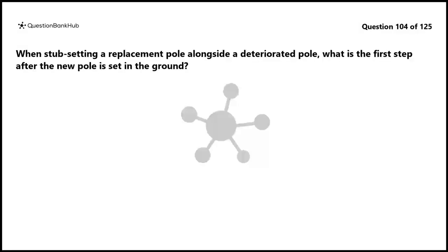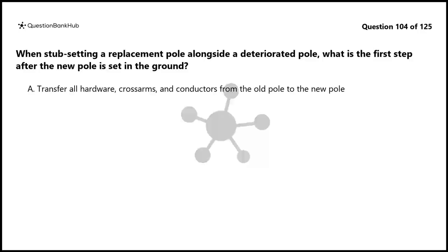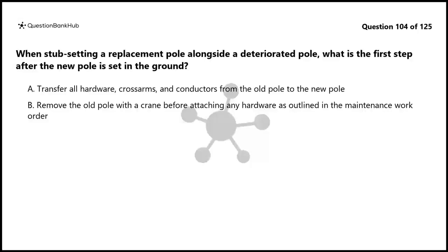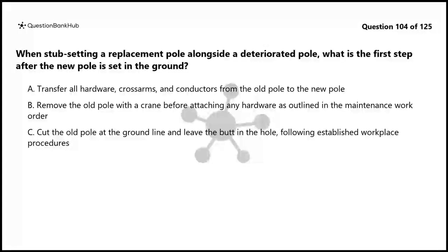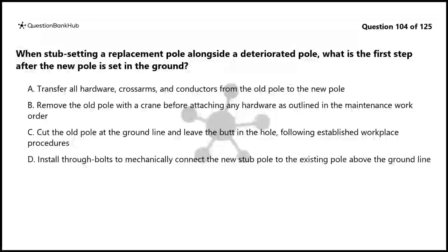Question 104. When stub setting a replacement pole alongside a deteriorated pole, what is the first step after the new pole is set in the ground? A. Transfer all hardware, crossarms, and conductors from the old pole to the new pole. B. Remove the old pole with a crane before attaching any hardware as outlined in the maintenance work order. C. Cut the old pole at the ground line and leave the butt in the hole, following established workplace procedures. D. Install through bolts to mechanically connect the new stub pole to the existing pole above the ground line.